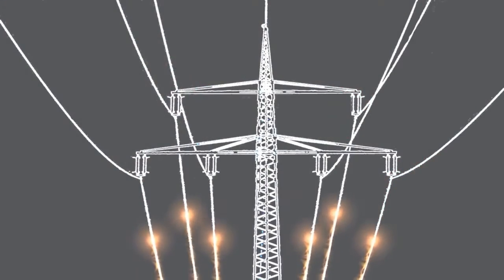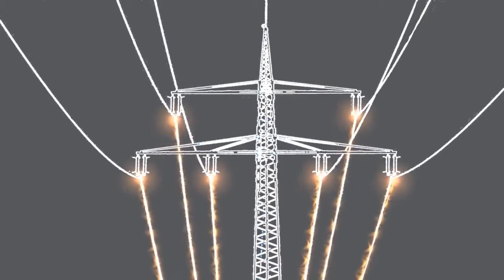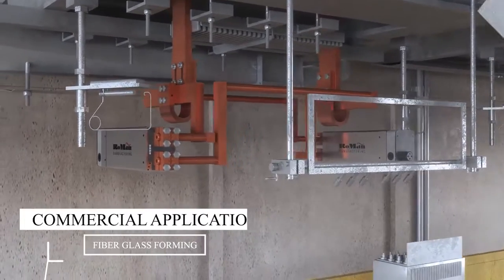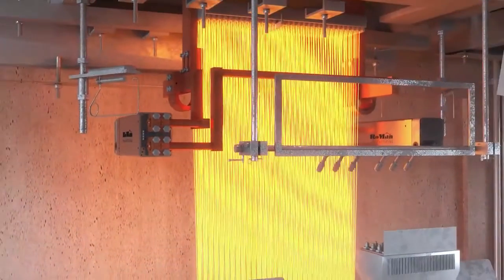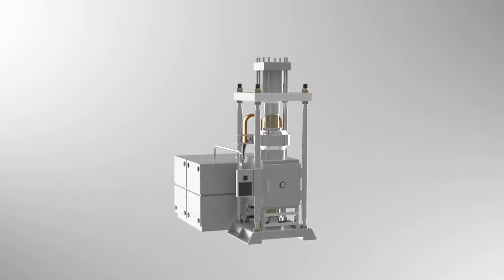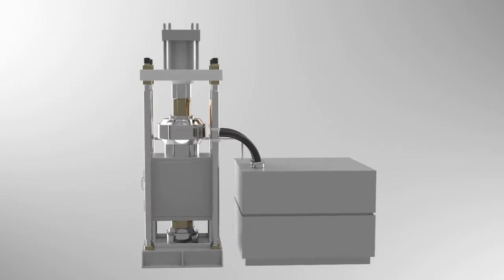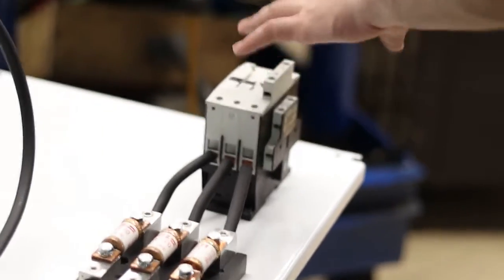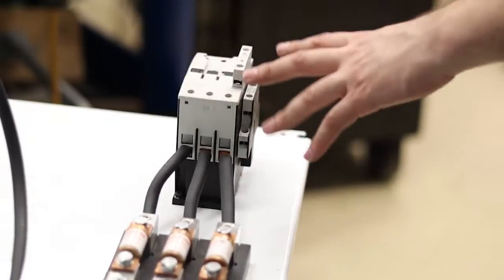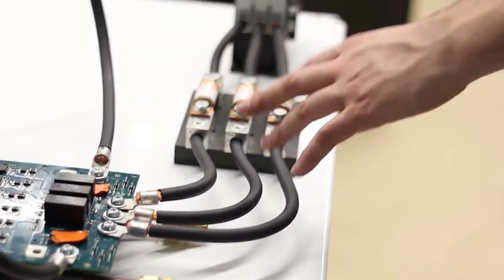What we must do is take in three-phase 480 volts from the power grid and convert it to a single-phase 650 volts at 50 amps output so that it can be useful for RoMan Manufacturing's customers, which may use our product for continuous resistance heating. This power conversion must be done through an active rectification process using silicon-carbide MOSFETs, which are more efficient than traditional passive diodes or active IGBT switches.